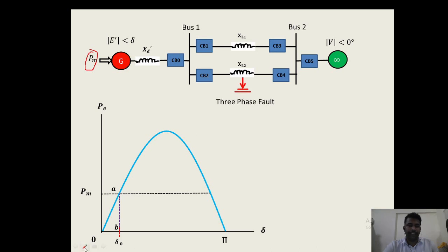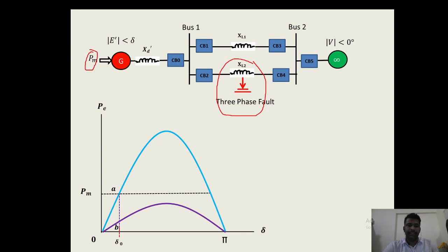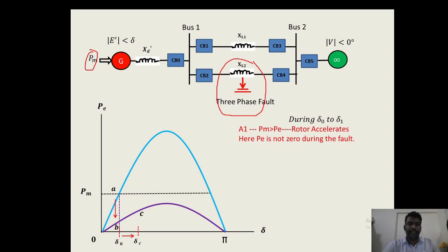When a three-phase fault occurs in one of the transmission lines, the power flow will be reduced and the point of operation will shift from A to B, and the power angle curve will be given by the second curve. At point B, mechanical power is greater than electrical power, so the rotor will start accelerating and the power angle will increase from delta_0 to delta_C, where the fault is cleared or circuit breakers operate.